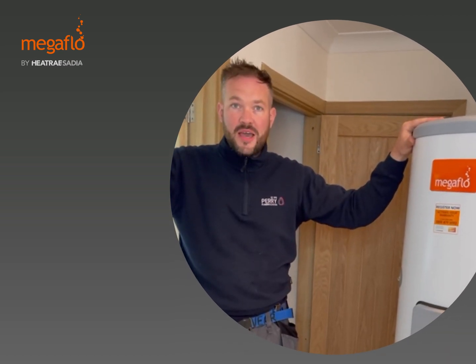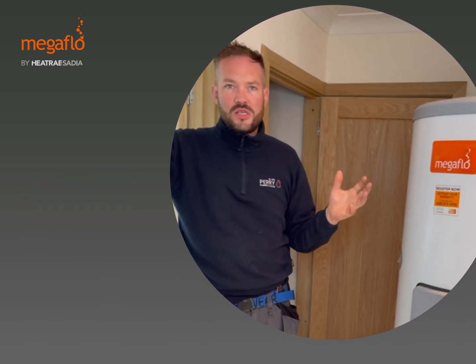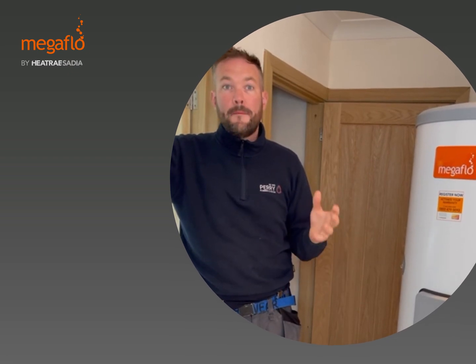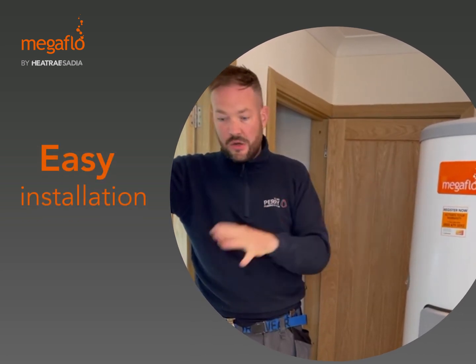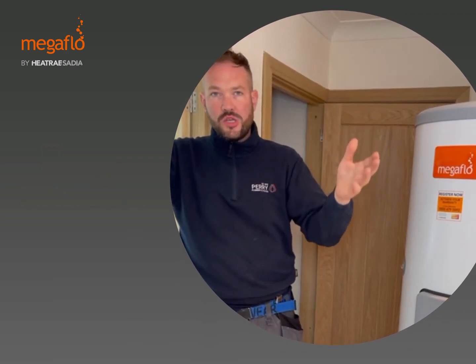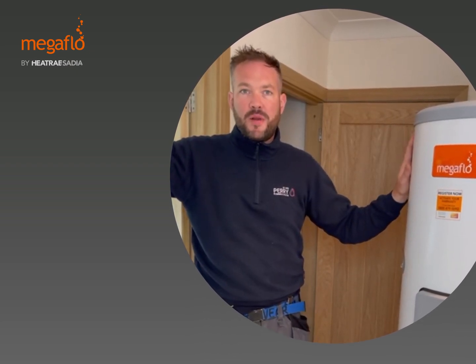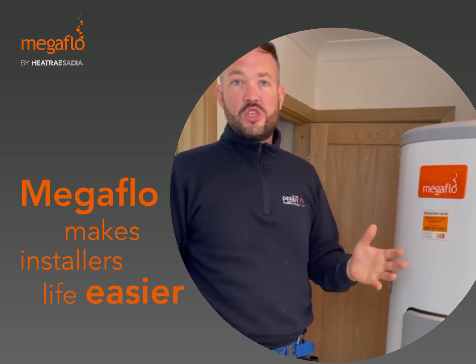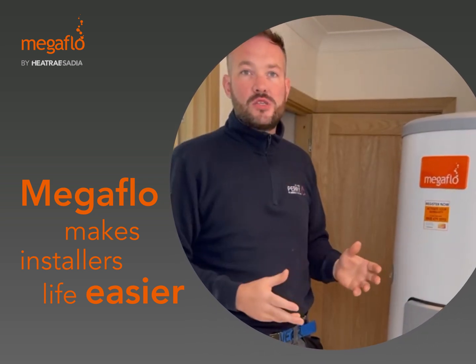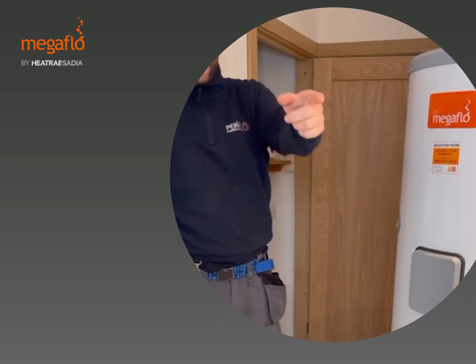What all us engineers love about the Megaflo product is the internal baffle. All the other cheap brands — all the other unvented water cylinders — require an external potable expansion vessel. Megaflow designed the internal baffle, so it's really easy. The instruction manual tells you how to do it, and you can also call Baxi and they'll tell you how to recharge the product. It never has to be replaced because it's internal — it's not a vessel hanging on the wall. This makes our life as an installer easier because it's one less product to install. I'll come back shortly and we'll see this product go in and see how the customer gets on.